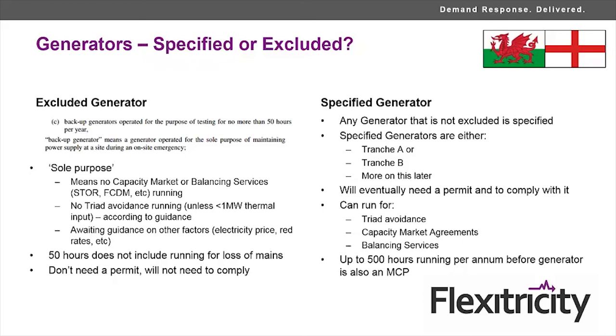Now, this is all about excluded generators. The excluded generators, testing for no more than 50 hours per year, well that doesn't include running for a real emergency. So if somebody cuts the cable to your site and you end up running your generator for several days, then that does not use up your 50 hours. An excluded generator doesn't need a permit and therefore doesn't need to comply with one, so there are no emissions limits in this legislation applying to excluded generators.